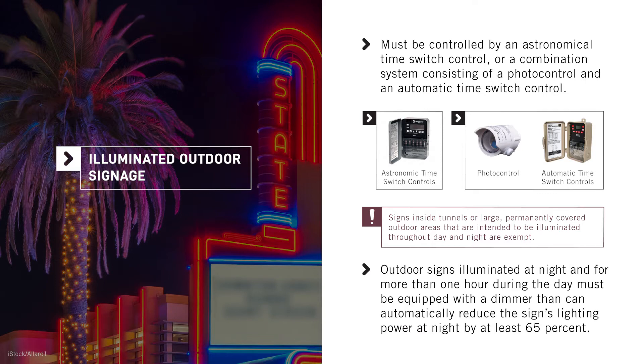In addition, outdoor signs that are illuminated at night and for more than one hour during the day must be equipped with a dimmer that can automatically reduce the sign's lighting power at night by at least 65%.